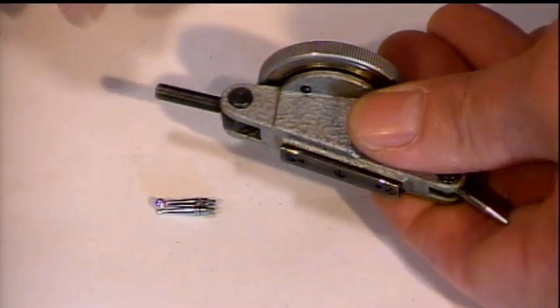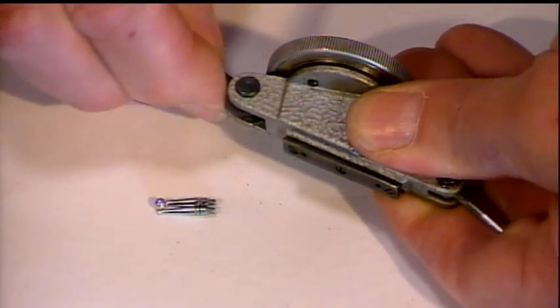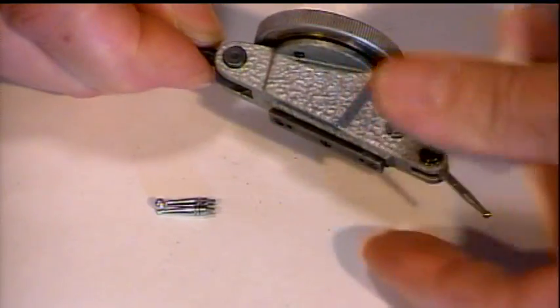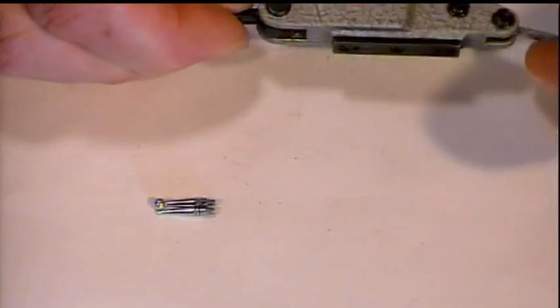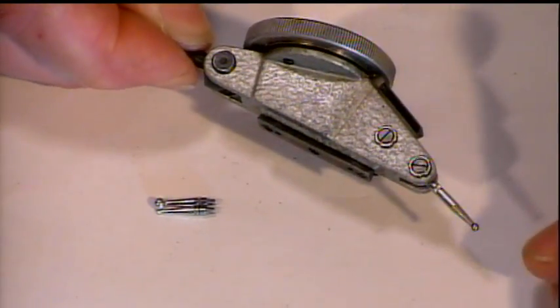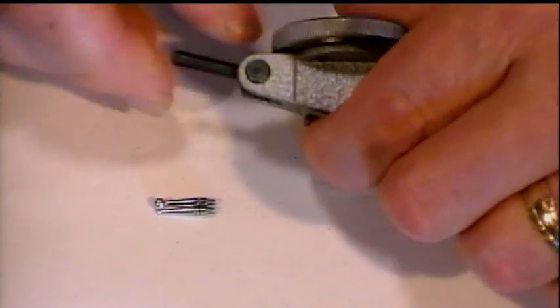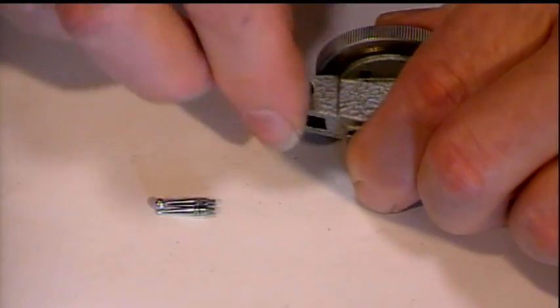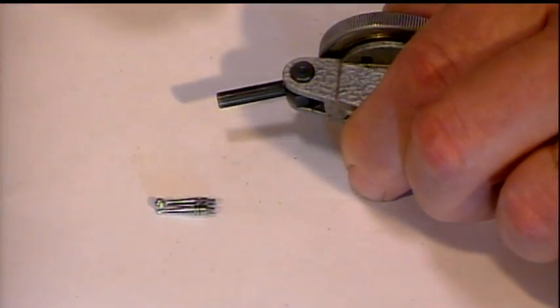This particular brand also has a stem on the back. That has to be tight enough that when the indicator is activated, it's not moving the whole indicator. What's the stem for? Staying still. Mounting in the height gauge, and it does swivel, but there should be quite a bit of tension in order to do that. Okay.